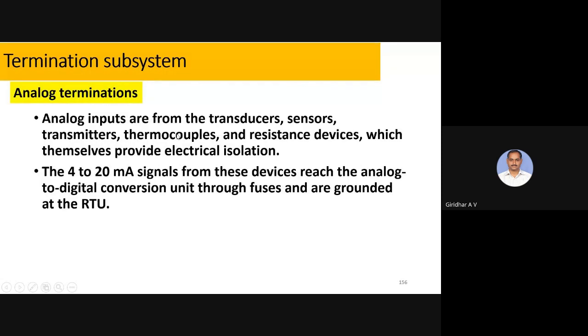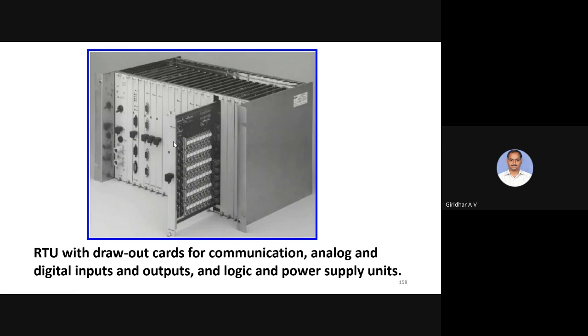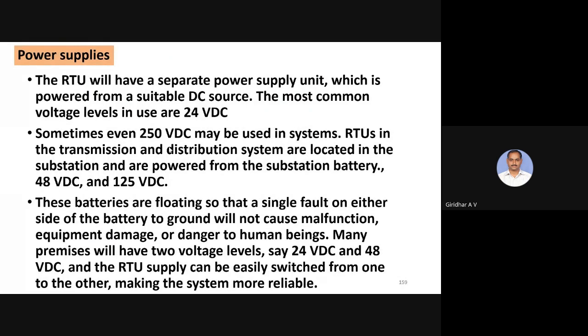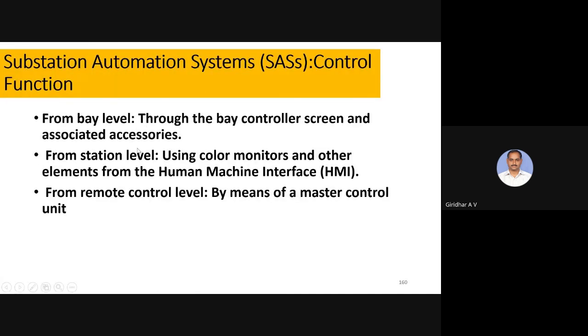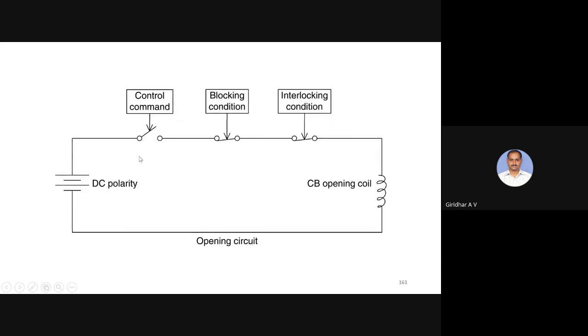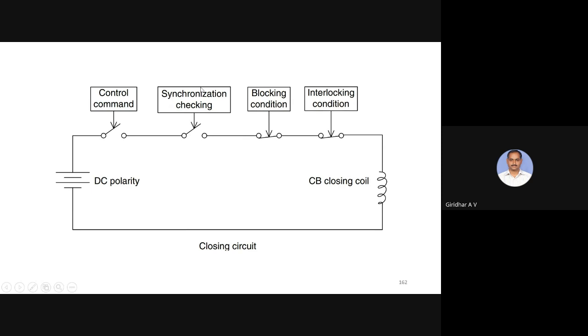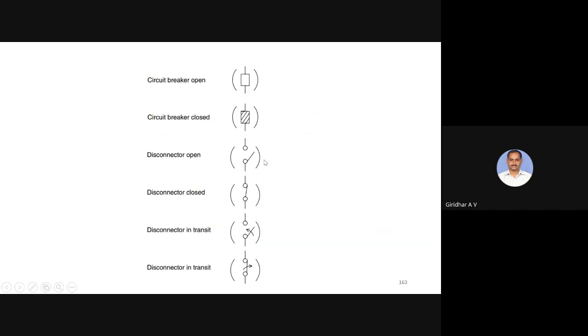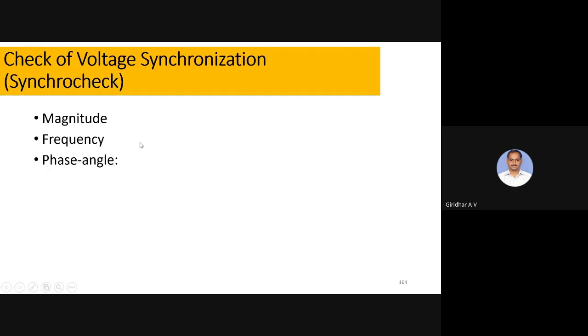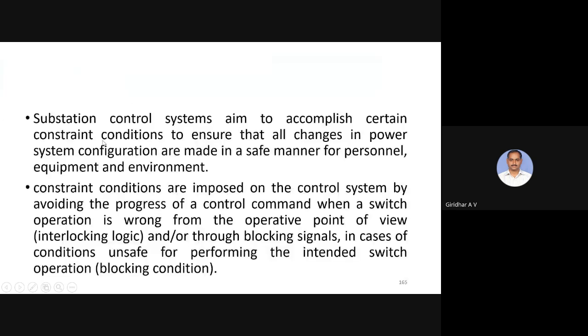Human machine interfaces. So these are particular RTUs. So you can see while opening the circuit of the circuit breaker, all these interlocking conditions, blocking conditions, in that way, the appropriate control command will be issued. Like that, all the things will be taken care of. So synchronization checking, opening the coil, closing the coil. So the magnitude, frequency, phase angle, everything will be checked.